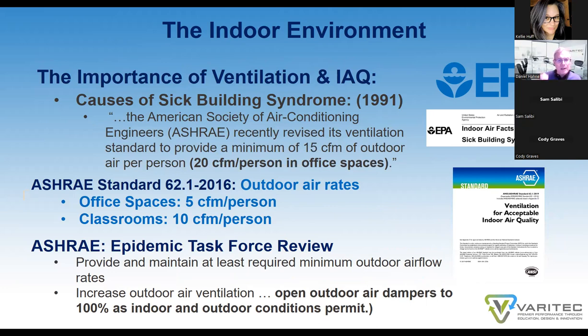of sick building syndrome. In 1991, ASHRAE elevated the outside air CFM levels to 20 CFM, 15 CFM, depending on the type of use of a building. ASHRAE Standard 62.1 2016, however, again reduced the outside air levels. Why? Well, because of the movement toward increased building efficiency to handle the carbon issue that we're facing globally in the world today. Reduce the amount of outside air to make HVAC systems more efficient. The less outside air you have to condition, the more efficient your system. So air flows were reduced back to 5 CFM per person and 10 CFM per person.